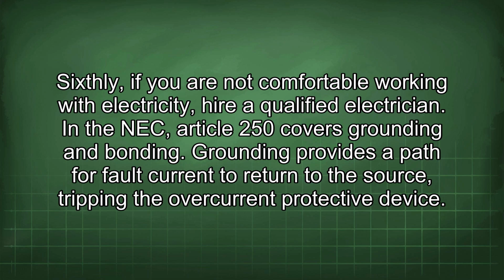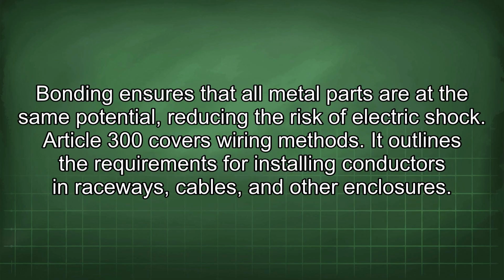In the NEC, Article 250 covers grounding and bonding. Grounding provides a path for fault current to return to the source, tripping the overcurrent protective device. Bonding ensures that all metal parts are at the same potential, reducing the risk of electric shock.